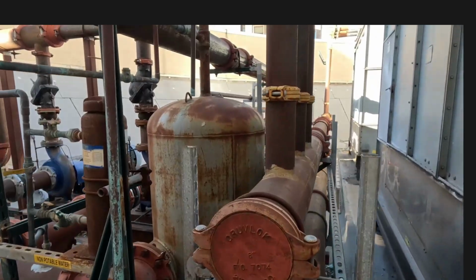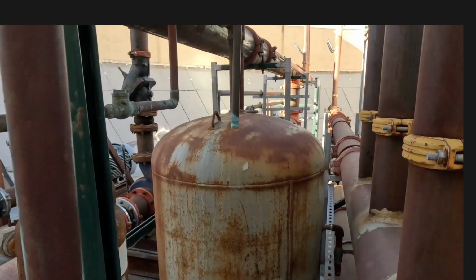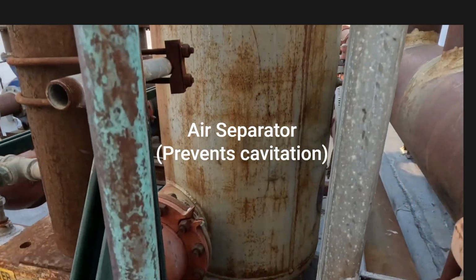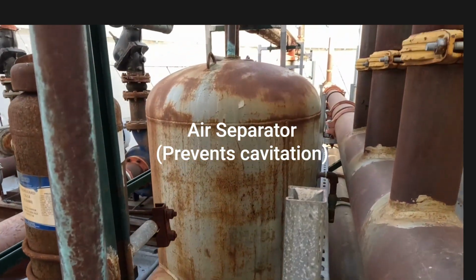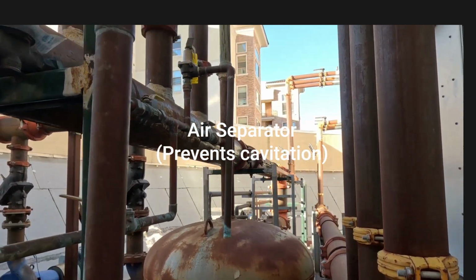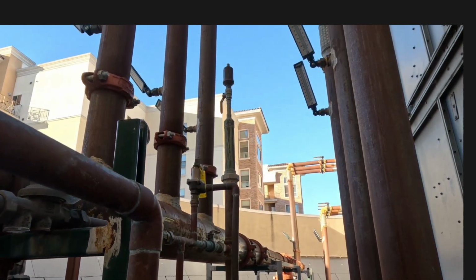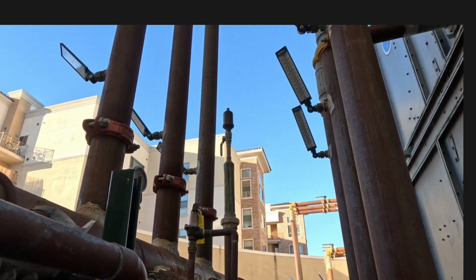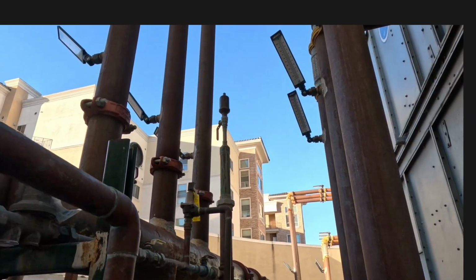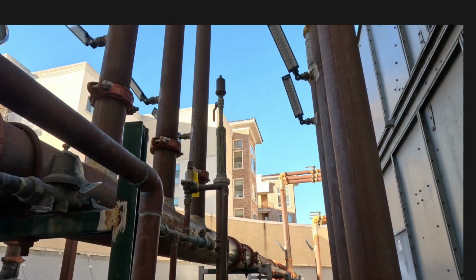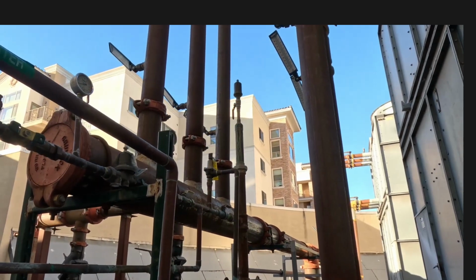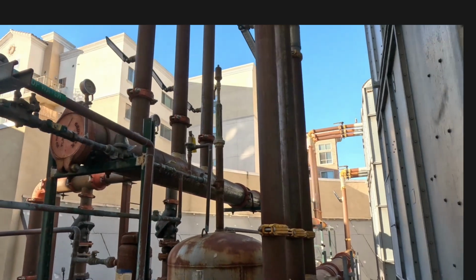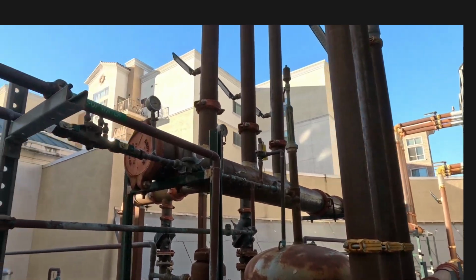Moving on here, this big tank right here. This is what we refer to as an air separator. That removes the air from the system, and you can see up there, we have an automatic vent with a valve open, so it's constantly venting whatever air it's grabbing from the system so the pumps won't get any of that air. So you can prevent cavitations.